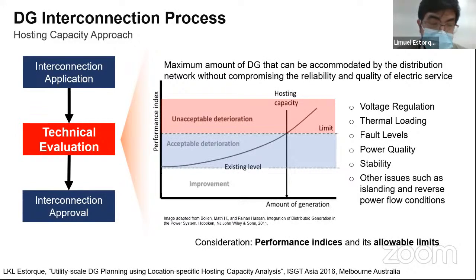These approaches were considered by many industry players and researchers through the application of various methods and state-of-the-art techniques. And most efforts have led to the assessment of what we call the DG hosting capacity. Hosting capacity is defined as the maximum penetration of DG, or aggregate capacity of DG, that can be accommodated without causing adverse impacts to the network. Hosting capacity is indeed an optimization problem wherein the analysis should return the maximum amount of DG capacity, considering that the technical issues or constraints in the network, such as voltage regulation, thermal loading, and power quality, would not be violated.